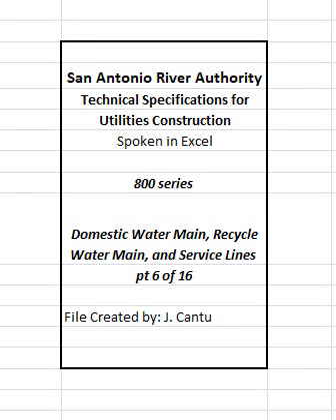P. Backfill. 1. Bedding and initial backfill for water mains. A. Well-graded gravels meeting the following requirements. Passing the 1/2 inch sieve 100%. Passing the 1/4 inch sieve 95 to 100%. The plasticity index shall be not more than 12 when tested in accordance with the TxDOT test method Tex-106-E.